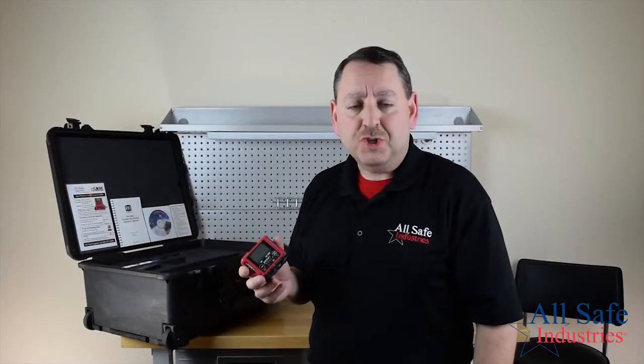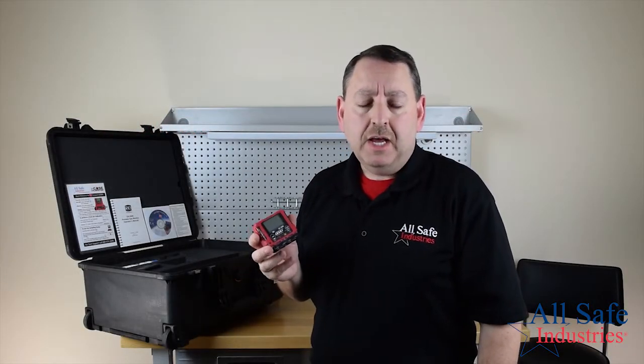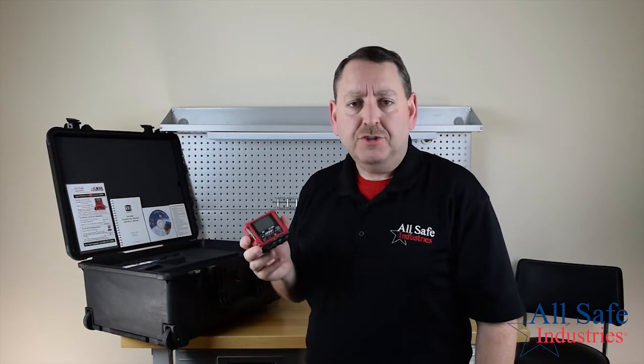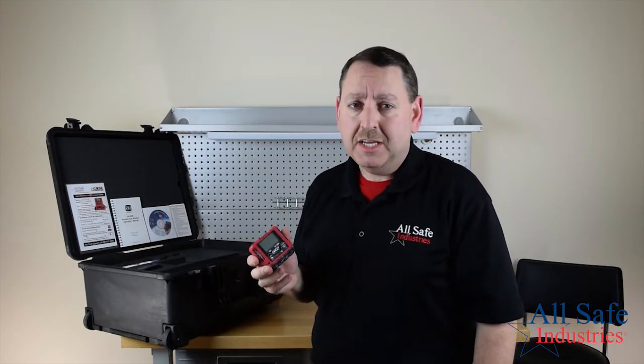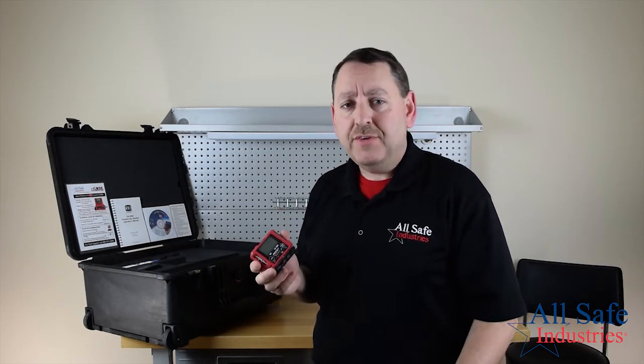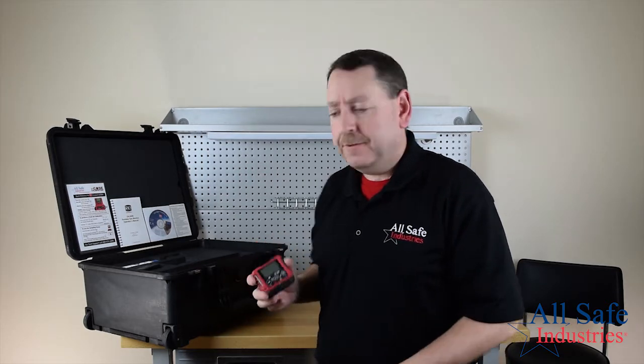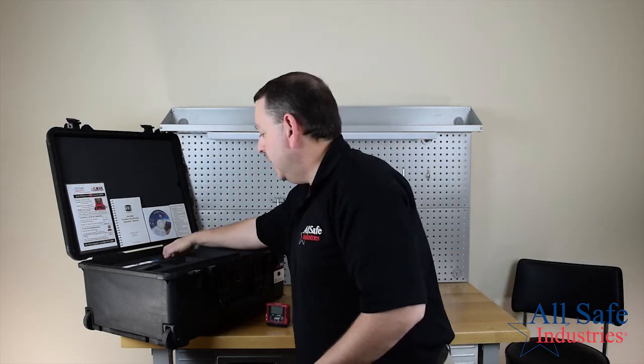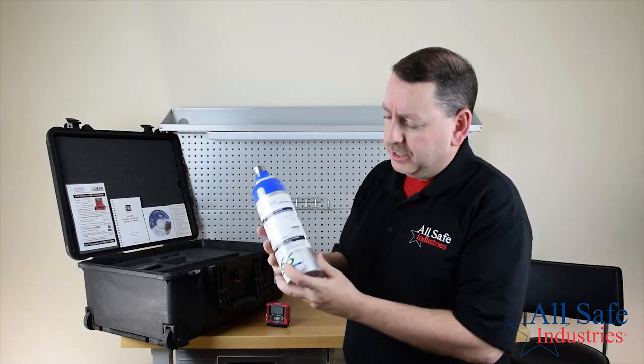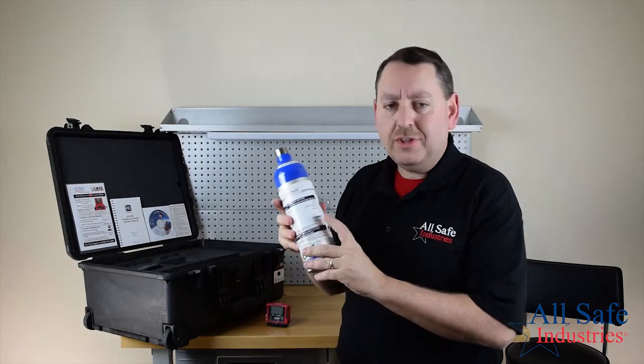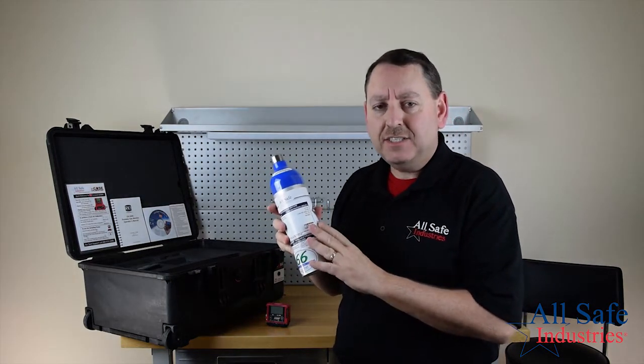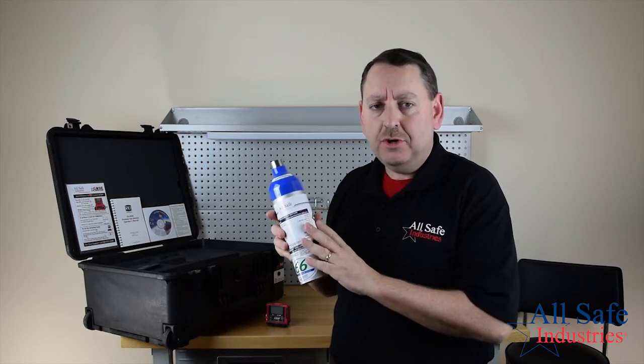Now I'm going to show you how to do a quick bump check on the meter. The manufacturer recommends that you do a function test or a bump check before each day's use. And you have everything you need to do that in your kit. You have your cylinder calibration gas. And the first thing you want to check on the calibration gas is to make sure that it hasn't expired. If your gas has expired, you want to get another cylinder on order right away.